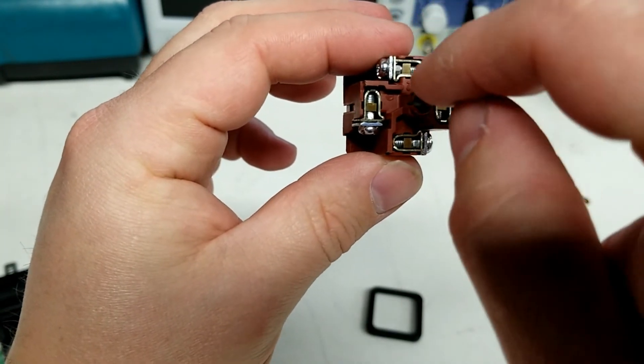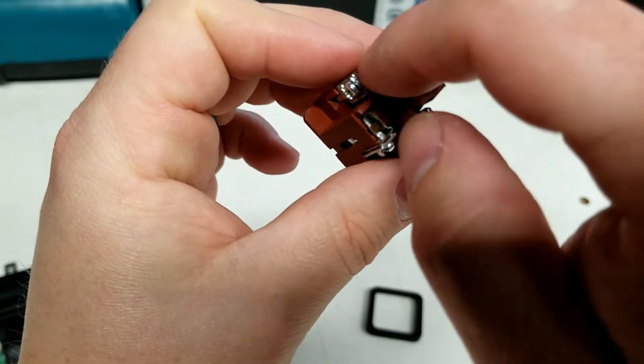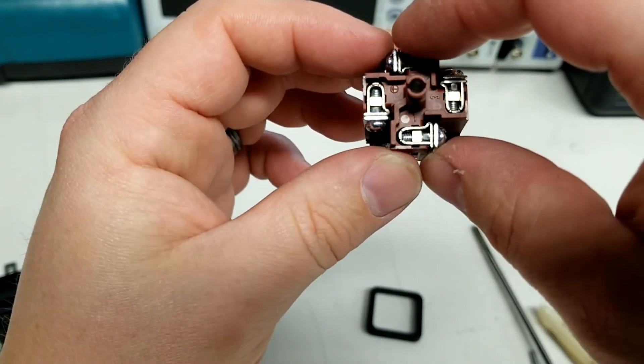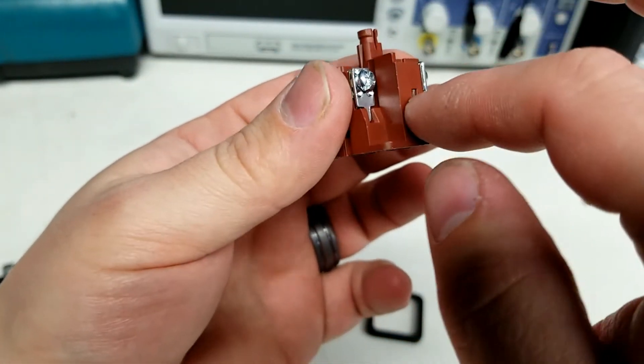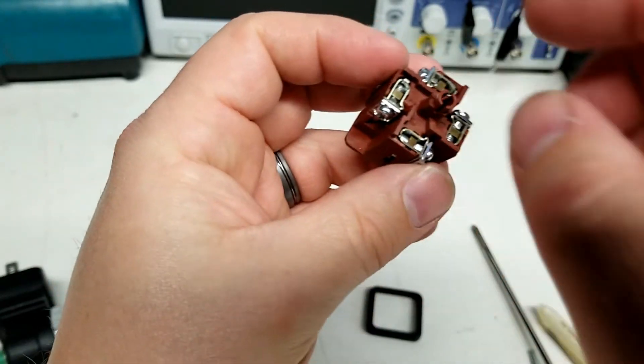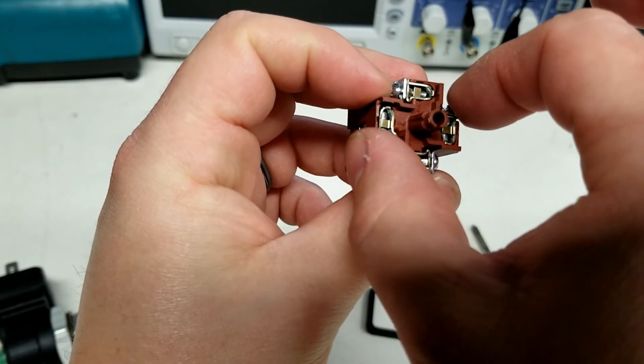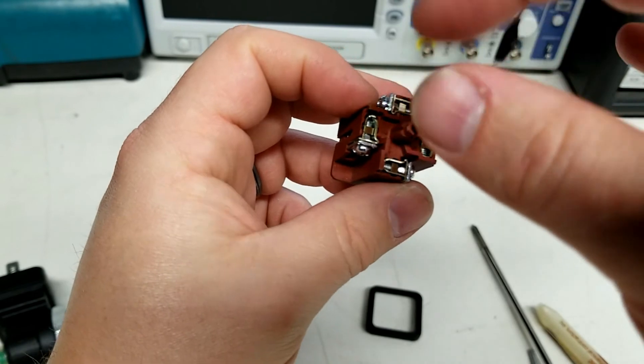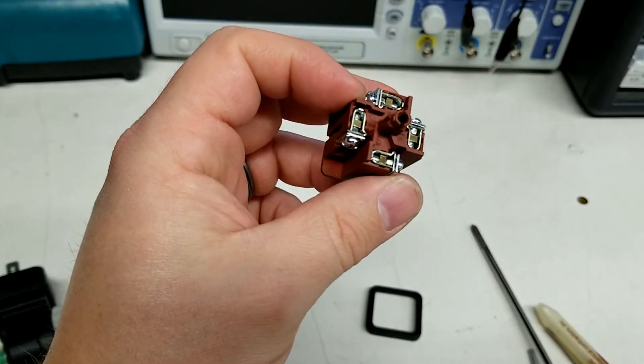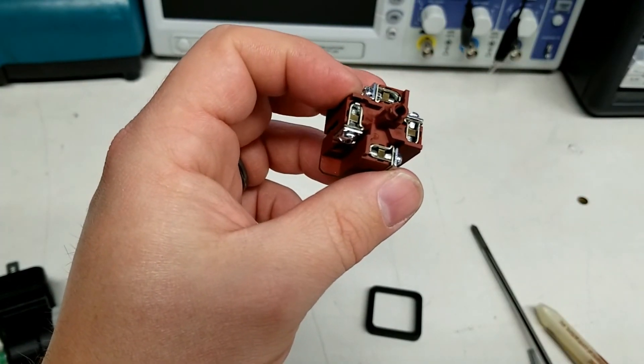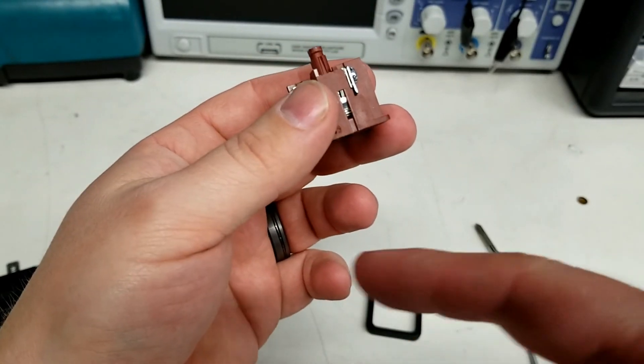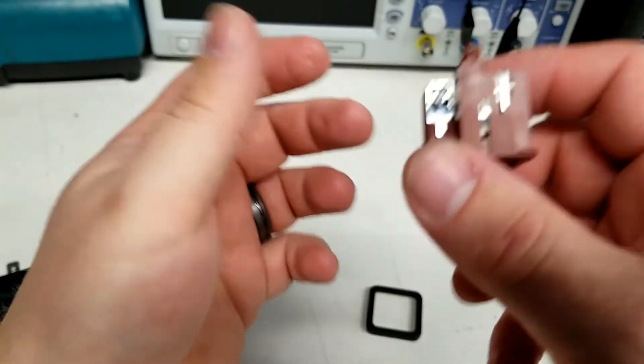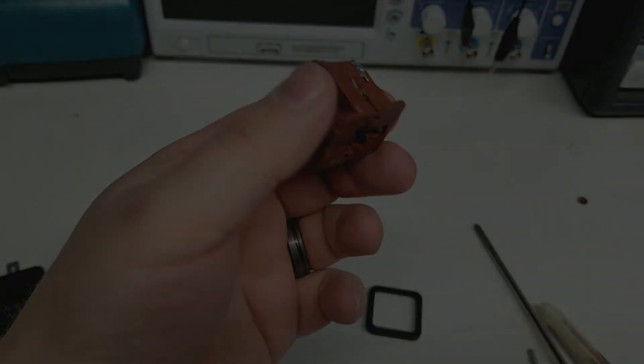These guys—it's usually two opposite pins—but these little clamps are notorious for coming a little loose. I've also seen these entire connectors short out. So if you pull this thing apart and remove your two wires from here, just twist your wires together and insulate them, or stick a wire nut on them. Then you've bypassed the sensor—you're still using your entire circuit, but you're bypassing the sensor. Then you can see if your problem's still there.